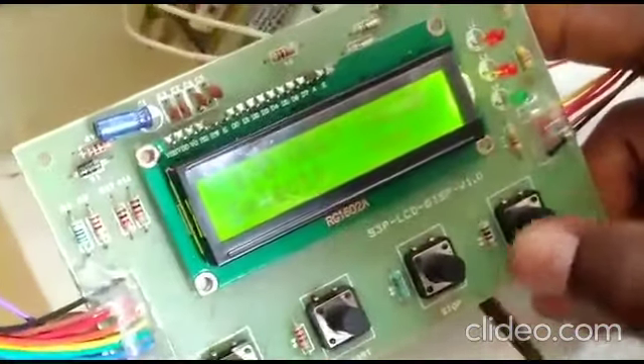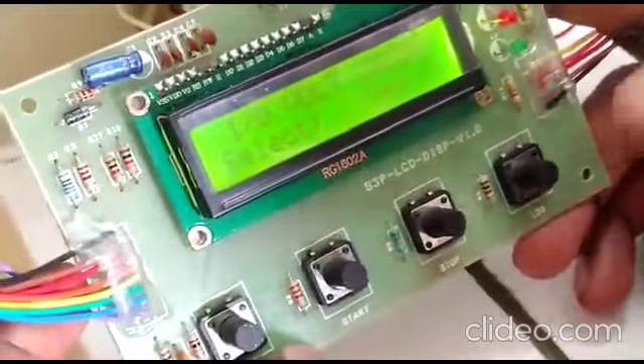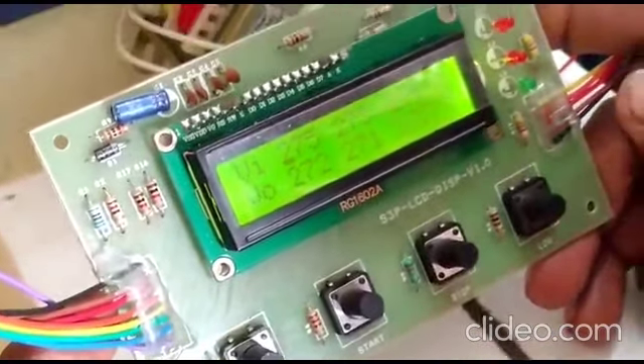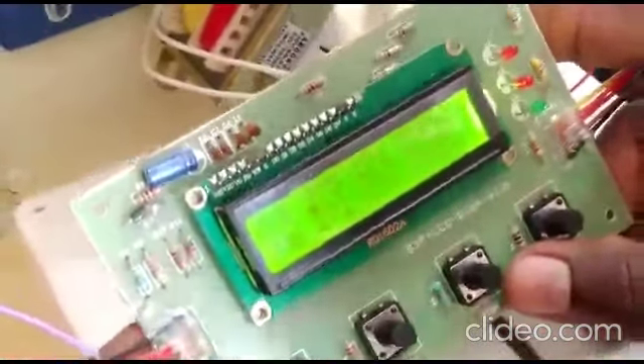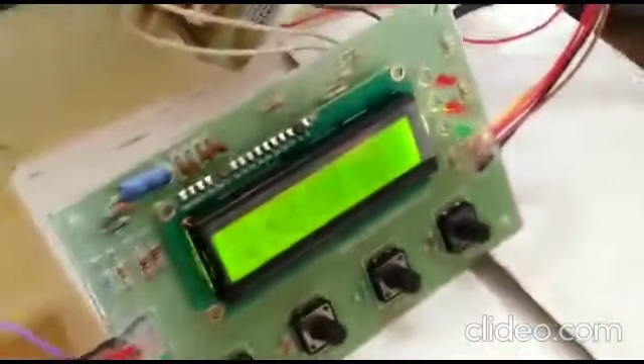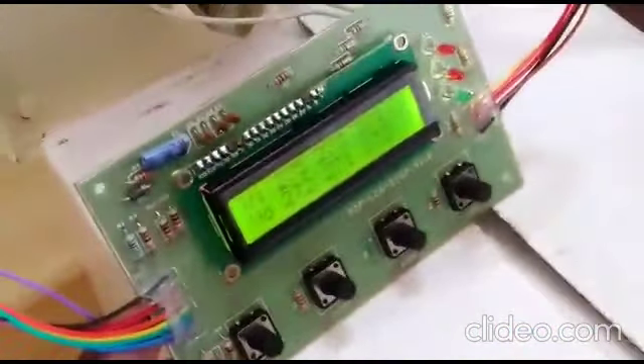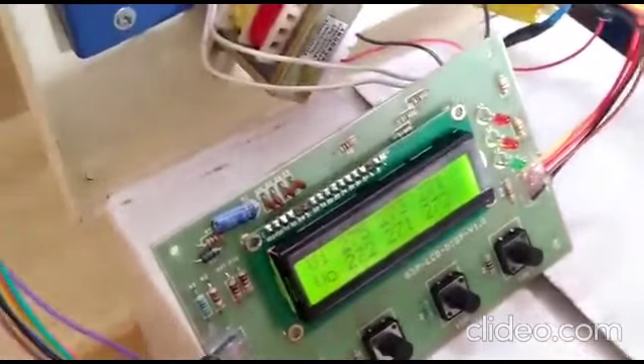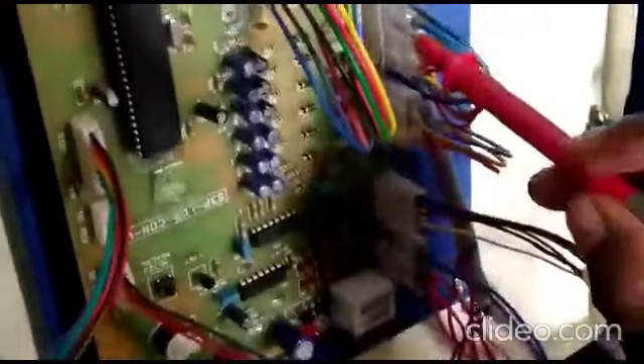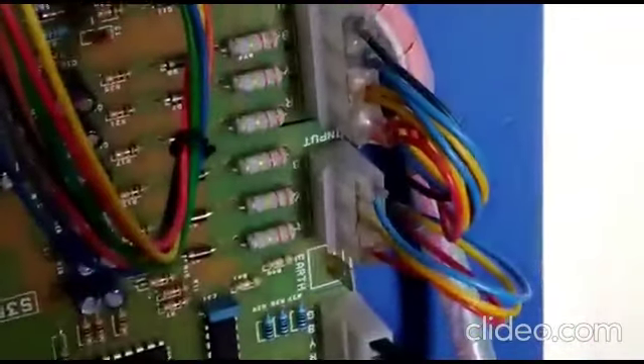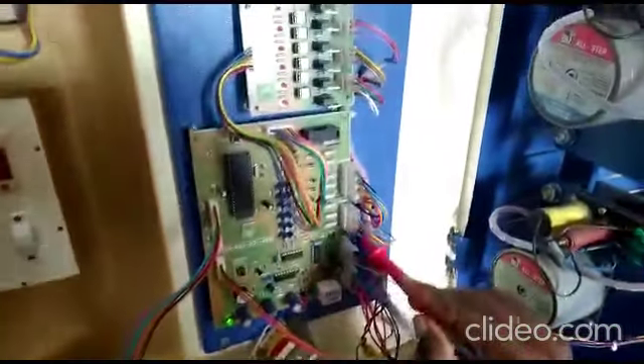Now for input output voltage calibration, select yes or no. We should select yes and press the log button. It shows some random analog values. I connect the multimeter to our board. These 3 lines are input lines. These 4 lines are output lines, including phase and neutral. First, we should enter the input R phase voltage. This is the input line, input R phase voltage.